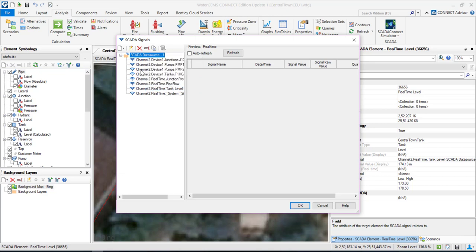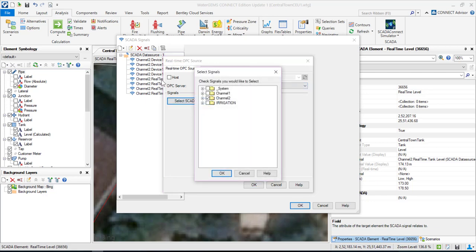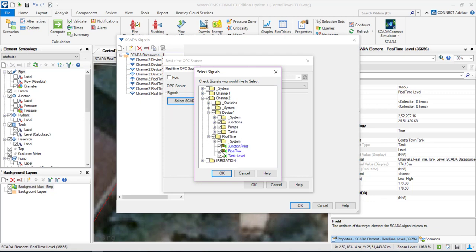If I click 'Edit Data Source', it will show all the configurations I used to set up this SCADA signal. As you can see, it's an OPC server — KEPServer version 5 is the server I'm using. This server has all these signals, and the ones useful in this model are located in Device 1 under real-time. I have specifically selected only those signals I want to map: the real-time junction pressures, real-time pipe flow, and real-time tank levels.